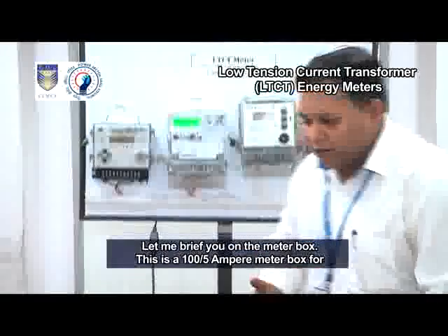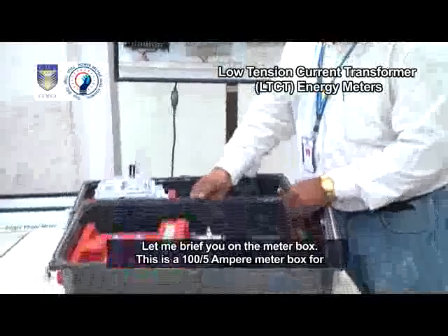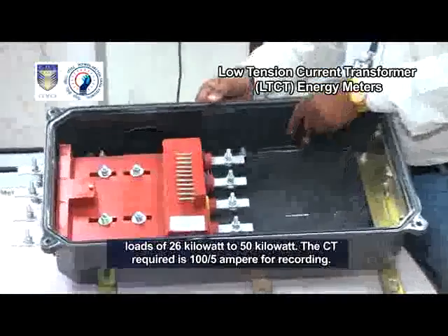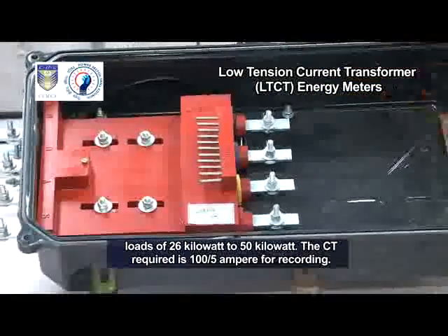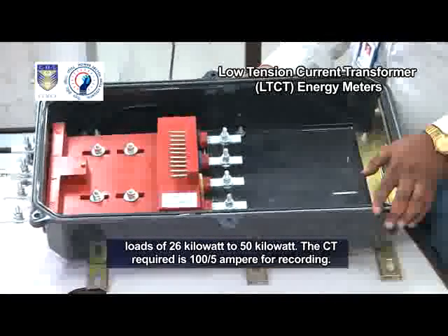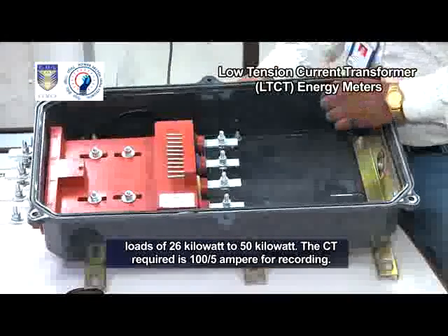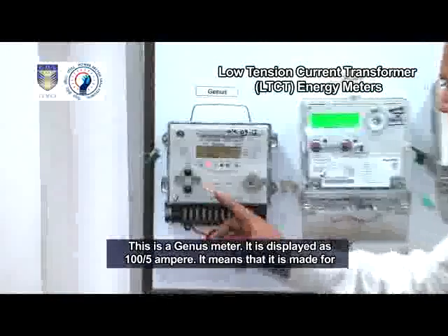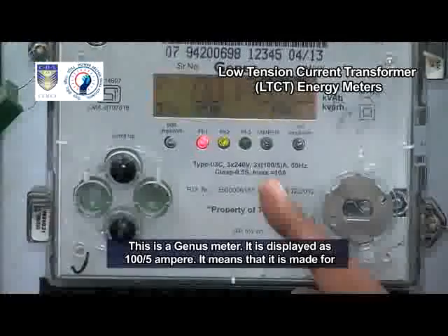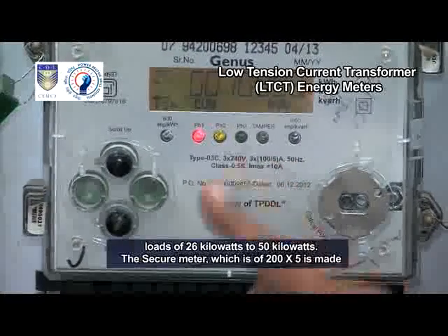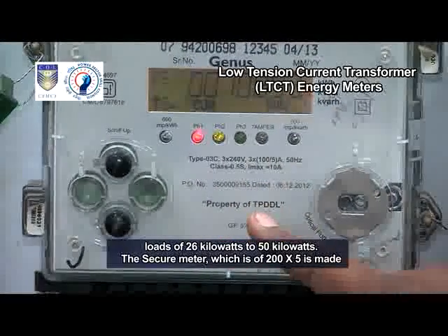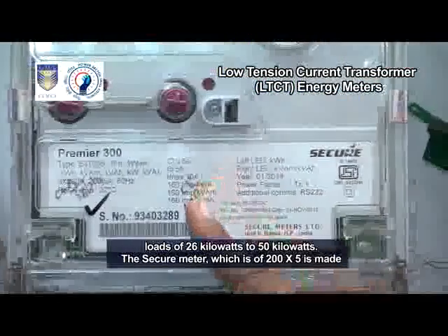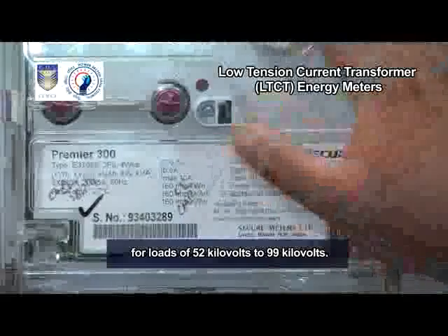Let me brief you on the meter box. This is a 100 by 5 ampere meter box for loads of 26 kilowatt to 50 kilowatt. The CT required is 100 by 5 ampere for recording. This is a Genus meter. It is displayed as 100 by 5 ampere. It means that it is made for loads of 26 kilowatts to 50 kilowatts. The Secure meter, which is of 200 by 5, is made for loads of 52 kilowatts to 99 kilowatts.